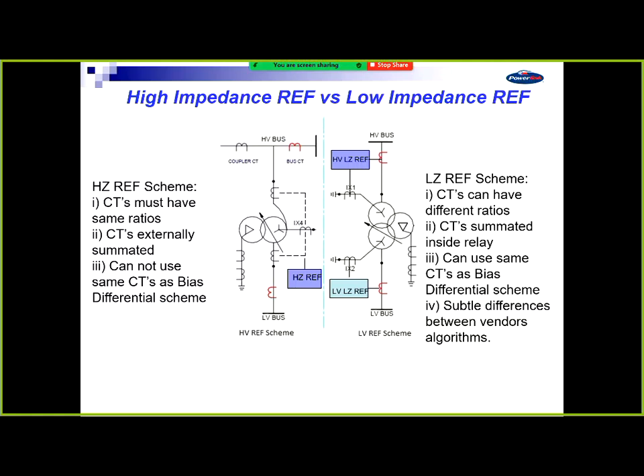The one on the left-hand side is a 275 kV arrangement. You can see that the auto-star has one high impedance scheme around the two windings, and well, this is actually an REF, not a high impedance REF. So there's one around, and you can see that neutral is just one CT. So off the neutral there, we've only got one winding.